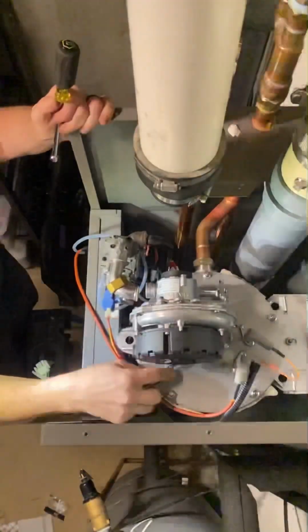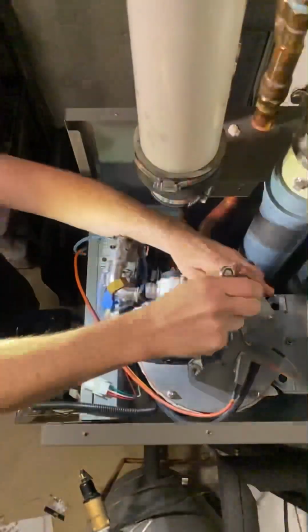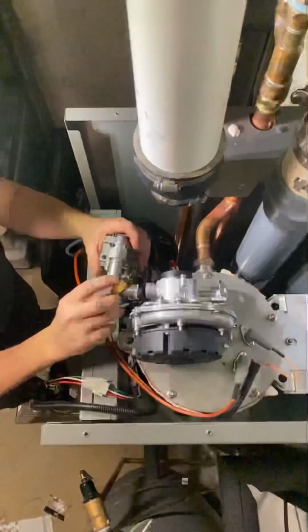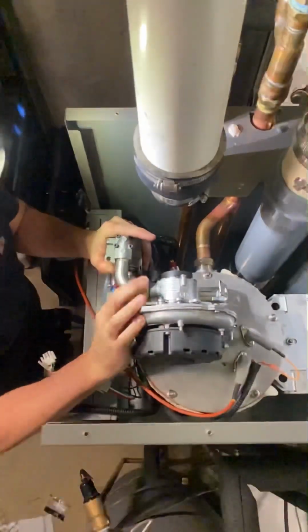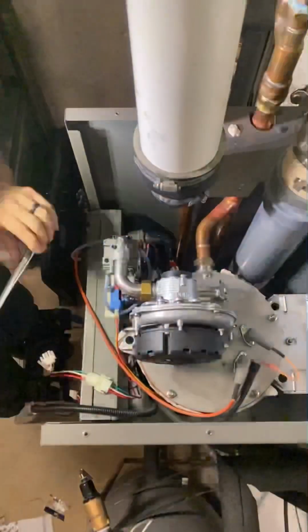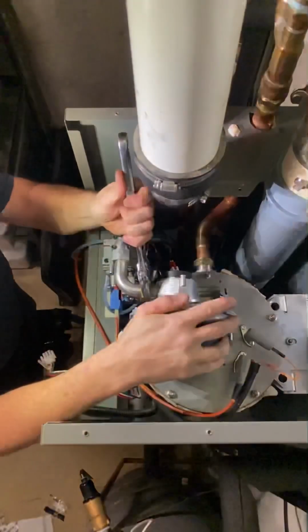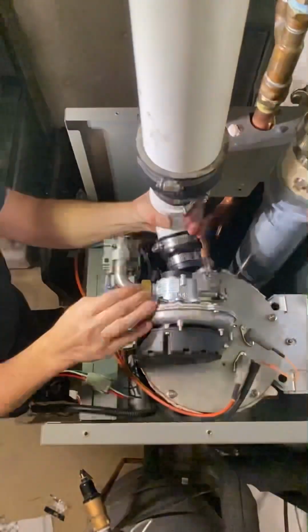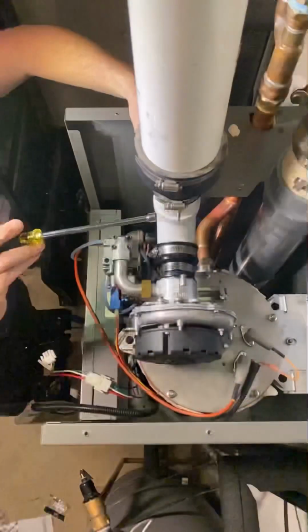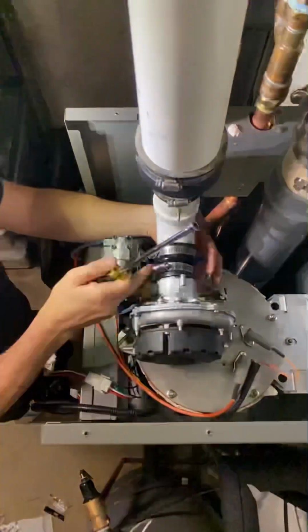Once you're done reassembling the boiler, the burner's dry, and you're ready to fire it up, it's time to get out your combustion analyzer and make any necessary adjustments to the gas valve. That's assuming you have one. If not, do not pass go, do not collect $200. You cannot properly start up or service a high-efficiency boiler without a combustion analyzer.